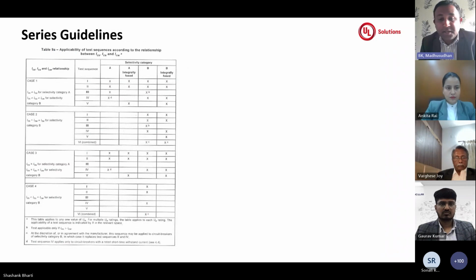As said in table 9A, based on the declaration, whether it is for selectivity category A for breakers or for selectivity category B, the standard gives clear guidelines with respect to the sequences. For example, if your short circuit ratings for ICU, ICS, and ICW, in some cases the ratings remain the same. In other declarations, the ratings will vary based on the design of the product. So from table 9A, we can see the list of tests that are applicable, and the standard clearly tells that some tests are not applicable, because the declared ratings coming from the manufacturers will suffice with the testing we are going to do in other sequences.